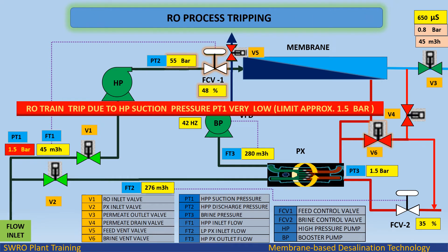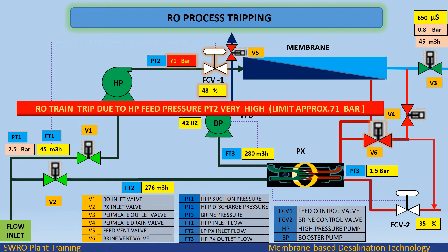RO train trip due to HP suction pressure PT1 very low, limit approximately 1.5 bar. RO train trip due to HP feed pressure PT2 very high, limit approximately 71 bar.